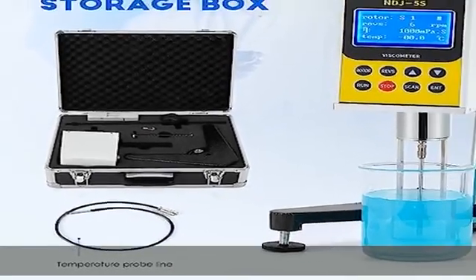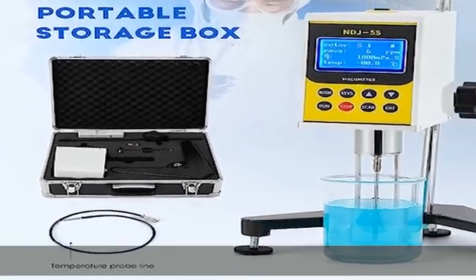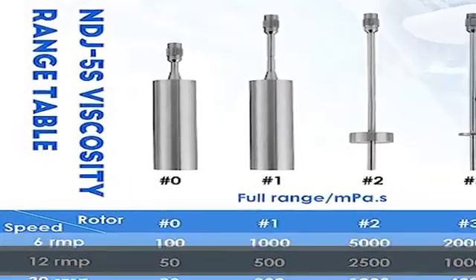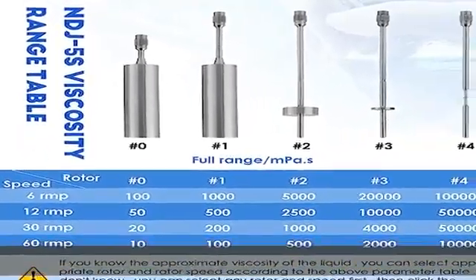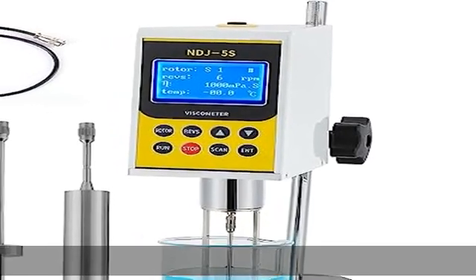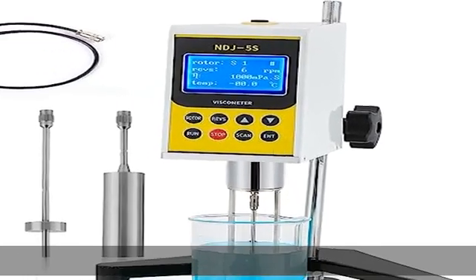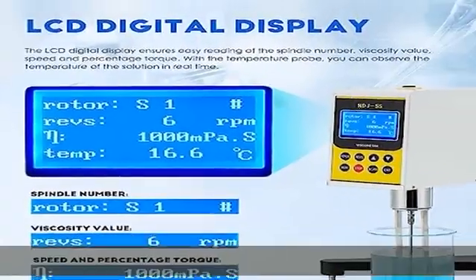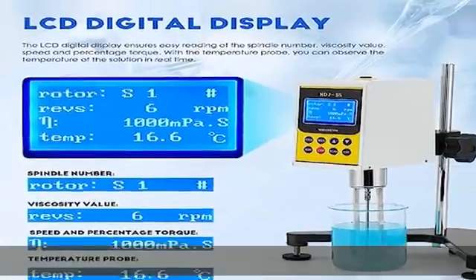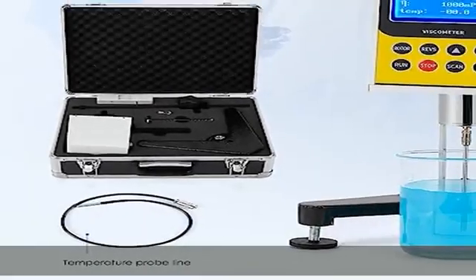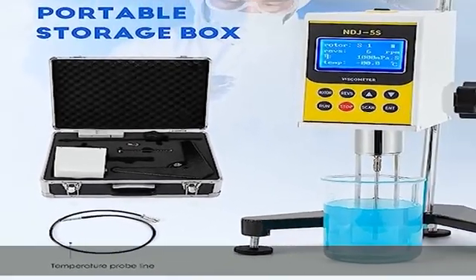Measurement error is plus or minus 3%, with 5 rotors: No. 0, 1, 2, 3, and 4, and 4 speeds: 6, 12, 30, and 60 RPM — which are composed of 20 combinations. You can determine viscosity as low as 1 mPa·s with the No. 0 rotor.